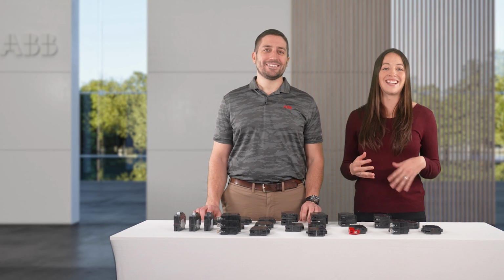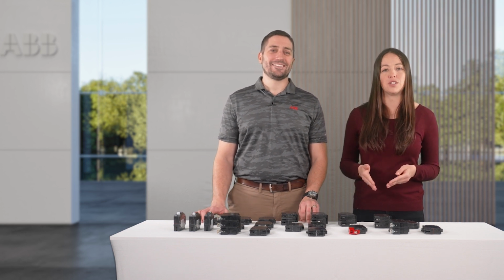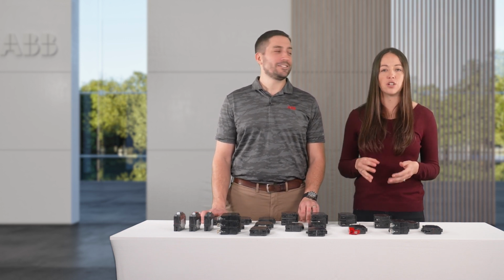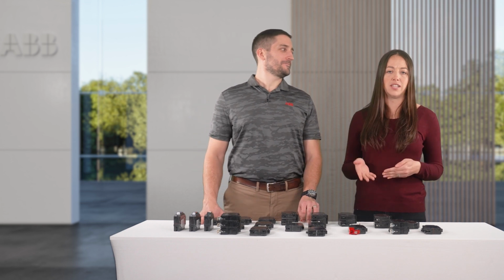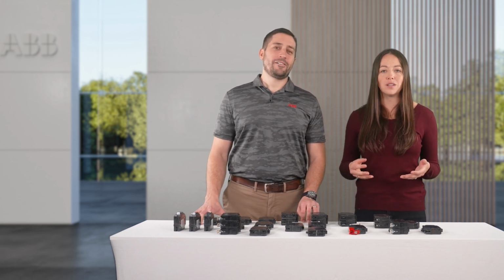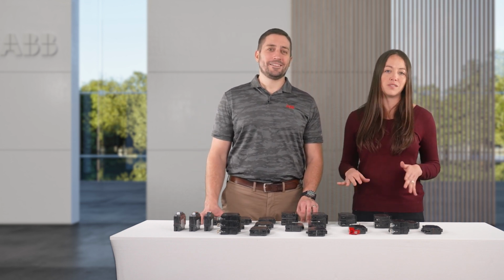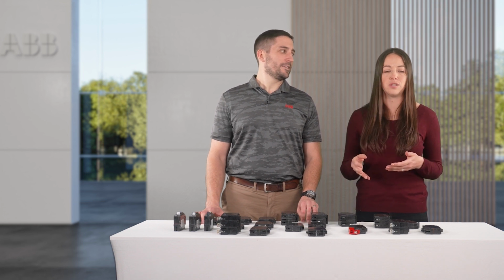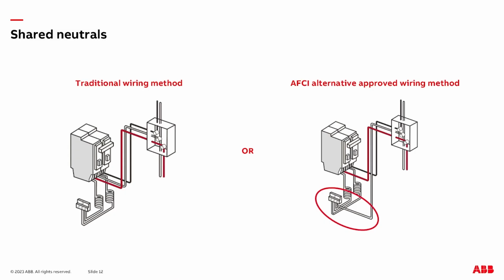ABB has patented technology in its arc fault circuit interrupters to identify abnormalities in a circuit's waveform that may be caused by arcing conditions. The technology does not rely on a clean neutral path, so you're not restricted in how you can mix or share neutrals. For new construction, you can choose between returning the neutral wire back to the breaker or to the neutral bar, whatever works best given your layout and space.